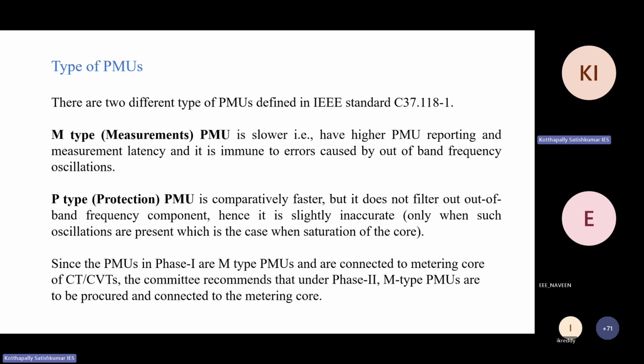Now let's see the difference between measurement PMU and protection PMU. In measurement PMU, the objective is measurement, so you get higher reporting data, but it is a little slower. In protection, you cannot take more time, so it should be faster. Protection type PMU is comparatively faster, but the data is not as accurate, whereas measurement PMU has higher reporting data but is a little slower.